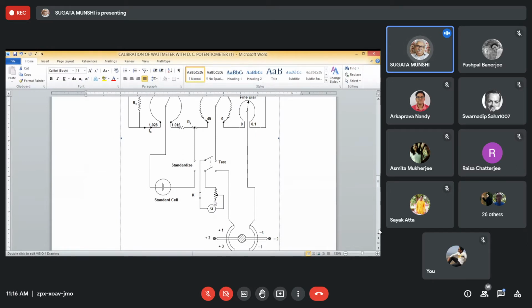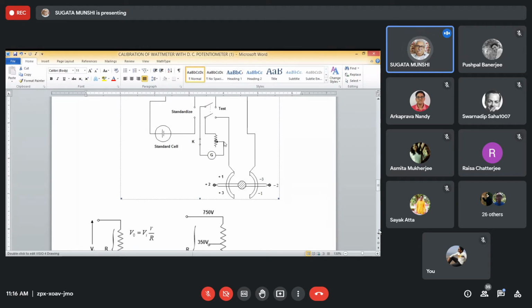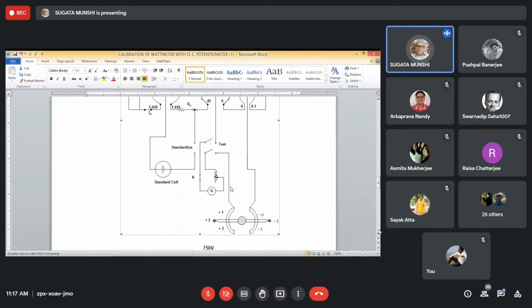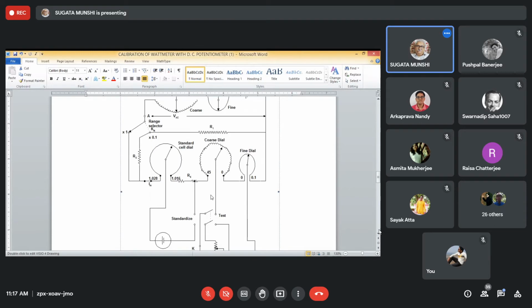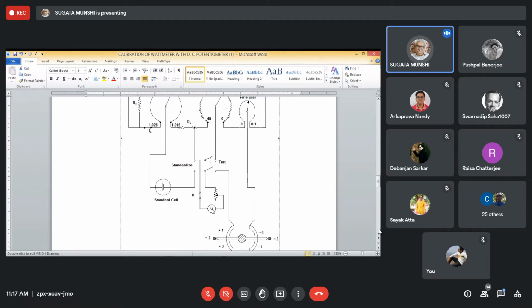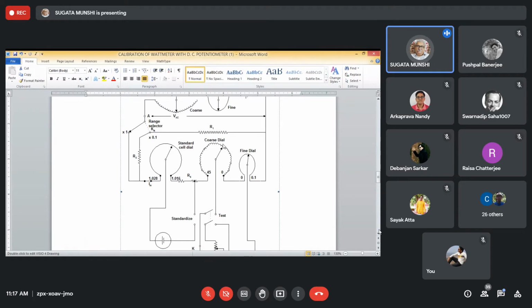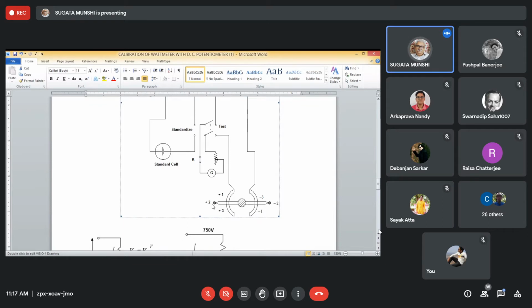The deflection of the galvanometer will change. There is a tap key in the series, not shown here, which is gradually tapped or pressed intermittently to check whether the galvanometer shows any deflection. At the same time, the position of the wiper on the coarse dial and fine dial is adjusted until the galvanometer indicates zero, null deflection. Under that condition, you read the coarse dial and fine dial values, and from these two values you add up to get the voltage of the unknown source connected between +2 and -2. This is the way.